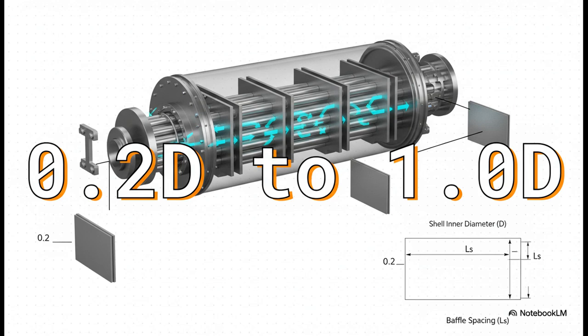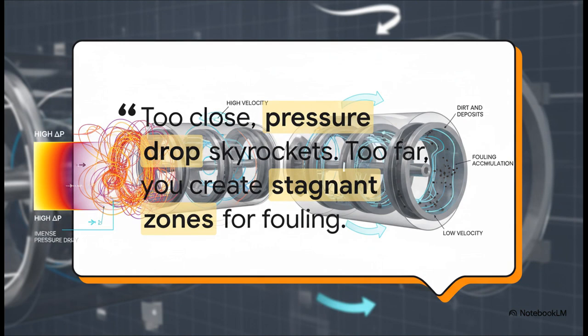And TEMA gives us a really handy rule of thumb for how far apart they should be, somewhere between 20% and 100% of the shell's inner diameter. And the reason this spacing is so critical is that it's all about finding the right balance. You see, if the baffles are too close together, you create this long winding path for the fluid, and the energy you need to push it through, your pressure drop, just goes through the roof. But if they're too far apart, you get these dead zones where the fluid barely moves, allowing all that dirt and gunk to settle out and foul up your exchanger.